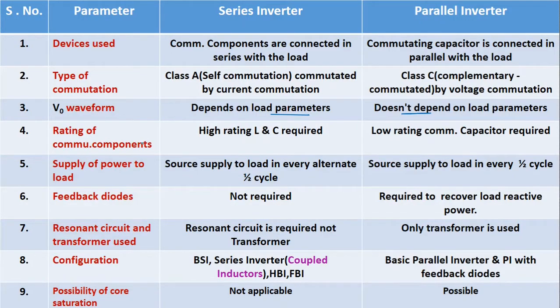Fourth one is rating of commutating components. In the series inverter, high rating of commutating components L and C is required, as the commutating capacitor is required to carry the load current continuously and also has to supply the load current in every alternate half cycle. Whereas in the parallel inverter, low rating of commutating capacitor is required, as the capacitor is not supposed to carry the load current continuously.